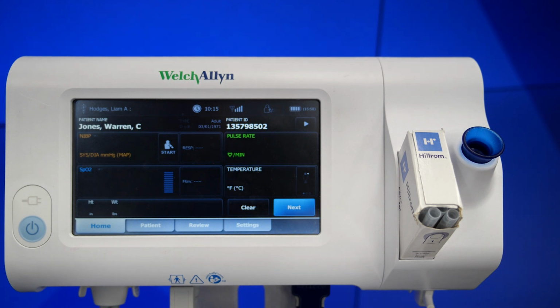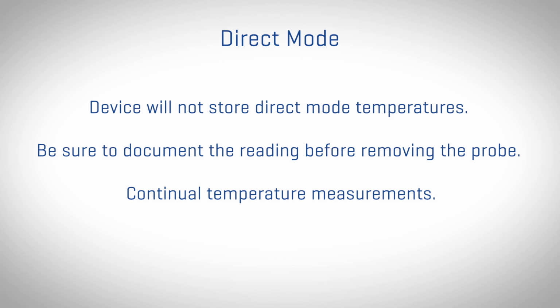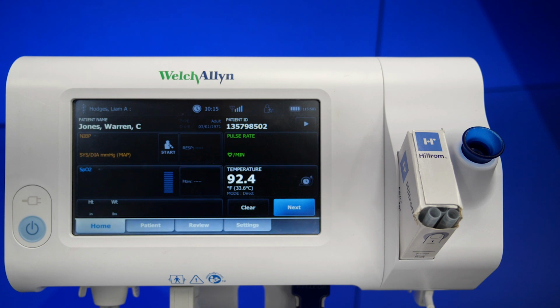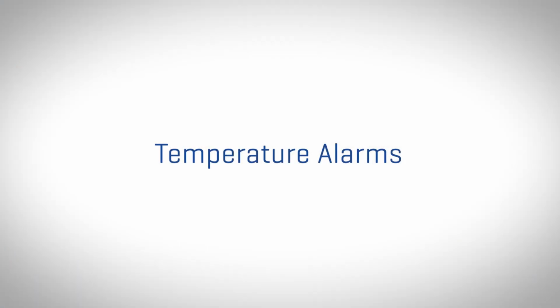In this mode, ensure the correct site is illuminated under the temperature site control. Before removing the probe from the application site, document the temperature. Remember, while in direct mode, the device does not store the temperature in memory, and the device will not beep to indicate the end of measurement. Once you're done with direct mode, remove the probe cover, return the probe to the well, and the device will reset to predictive mode. On some Welch Allyn devices, alarms are available within the intervals profile.